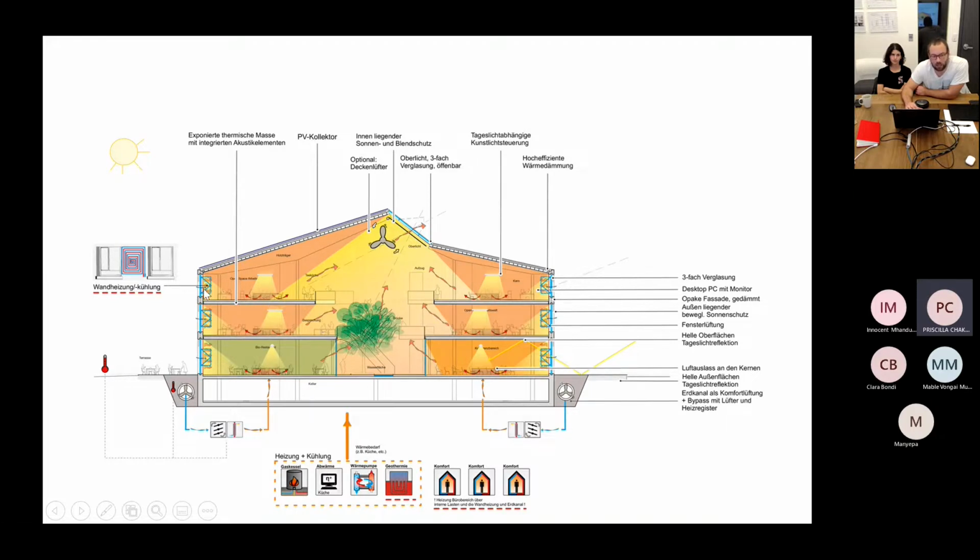So we said, okay, an option is we add to this rammed earth wall a radiant heating and cooling function. So there's tubes embedded in the rammed earth, so that we have a wall heater basically, or cooling over the wall to the space. Also, obviously, the skylight here is oriented to the north, so we don't get a lot of direct radiation, but we get a lot of daylight. It has a geothermal field. We're using the energy from the soil as a renewable energy source. And it was also talked about a lot, this adaptive comfort, that we can extend the comfort range.